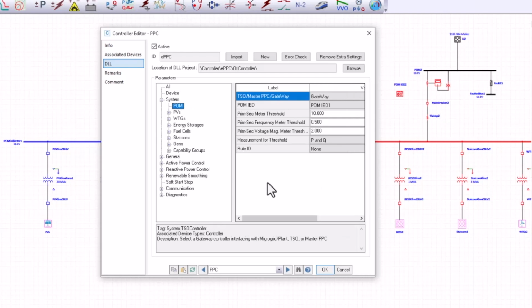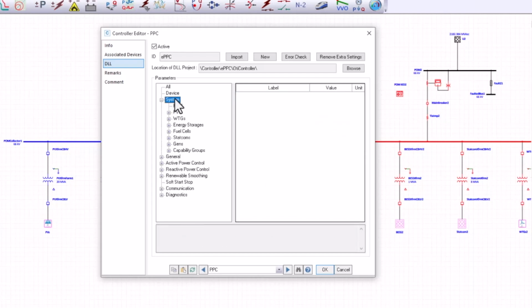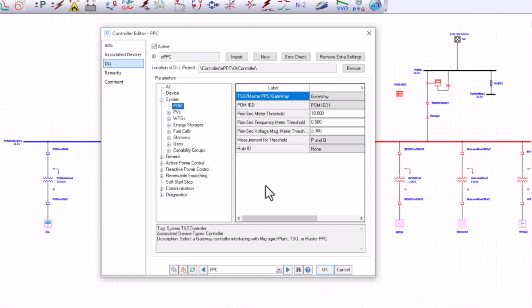In the system setting, we define some of the more basic and system level settings of EPPC. For example, if our POM has a redundancy, it needs to be defined here. If we are using a specific rulebook for the capability of the entire plant, again, it needs to be defined here. And if our primary assets and our generating units have any specific capability requirements, they can be defined in the system setting of EPPC.